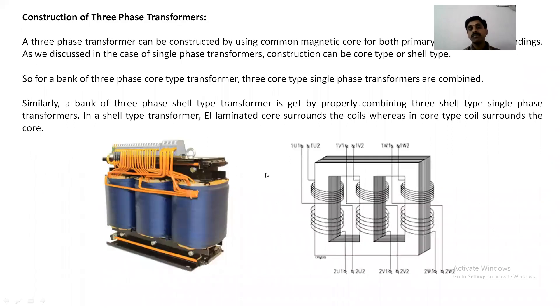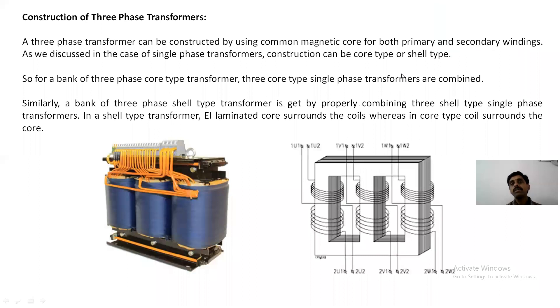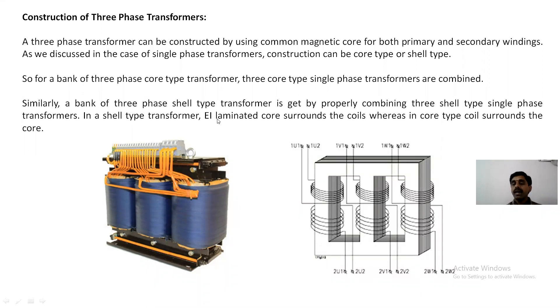Construction of three-phase transformers can be of core type or shell type, just like single-phase transformers. A common magnetic core is used for both primary and secondary windings across all three phases. To form a three-phase core type transformer, we take three single-phase core type transformers; similarly for shell type. In shell type, the EI laminated core surrounds the coil, whereas in core type, the coil surrounds the core.